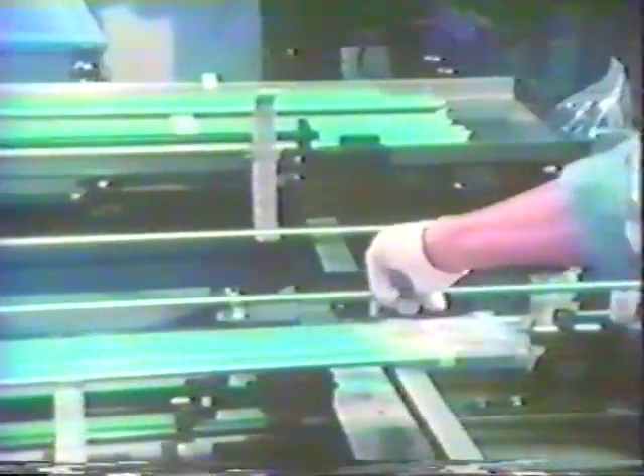Tubes are meticulously inspected before being loaded with fuel. The purpose is to check on wall thickness, diameter, and for any flaws that might contribute to rod failure. Tube integrity is assured by ultrasonic and X-ray tests. The rods are etched in a mild acid solution and then rinsed in clear water. Another step to assure durability in service. Random rod samples are cut apart for microscopic examination. X-rays of pellet-holding tubes verify the loading and welding processes.